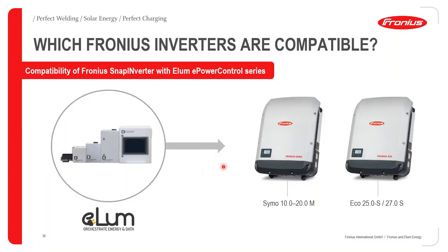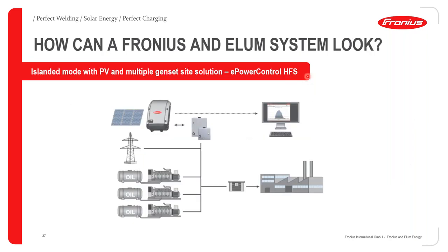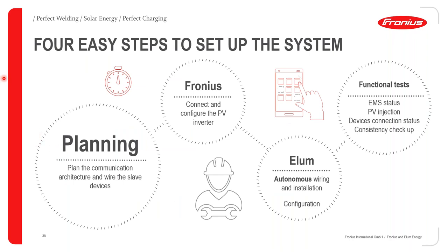Key compatibilities between ELUM and Fronius: all snap inverters are compatible with PV genset solutions. For ELUM systems, which are mostly commercial installations, Fronius recommends the Symo 10–20 kW and the Eco 25–27 kW commercial range. Setting up the system is straightforward: plan the communication architecture, identify slave devices, connect and configure the PV inverters.